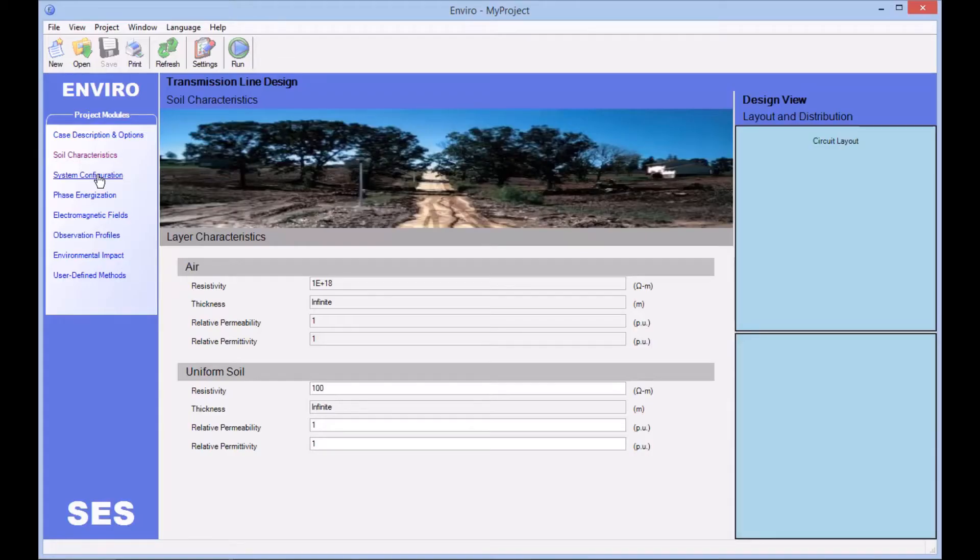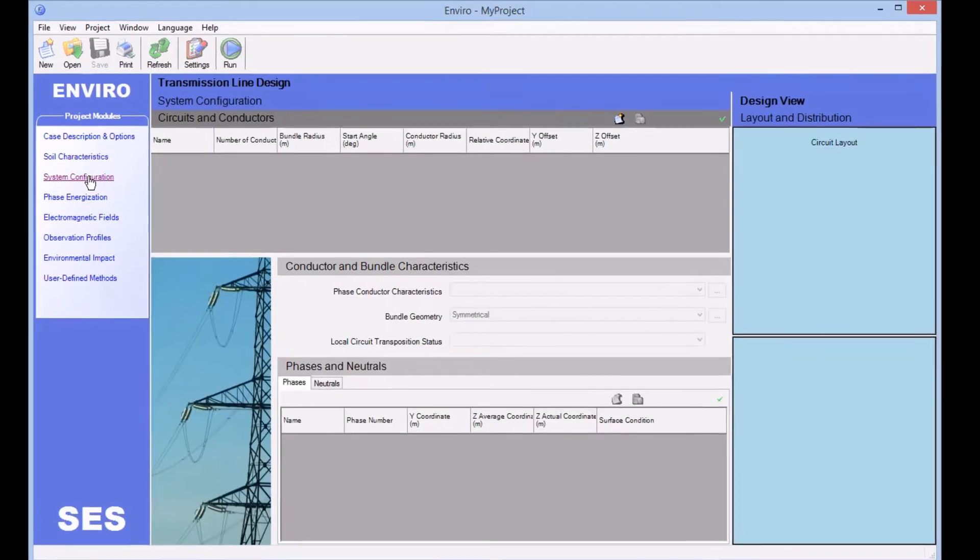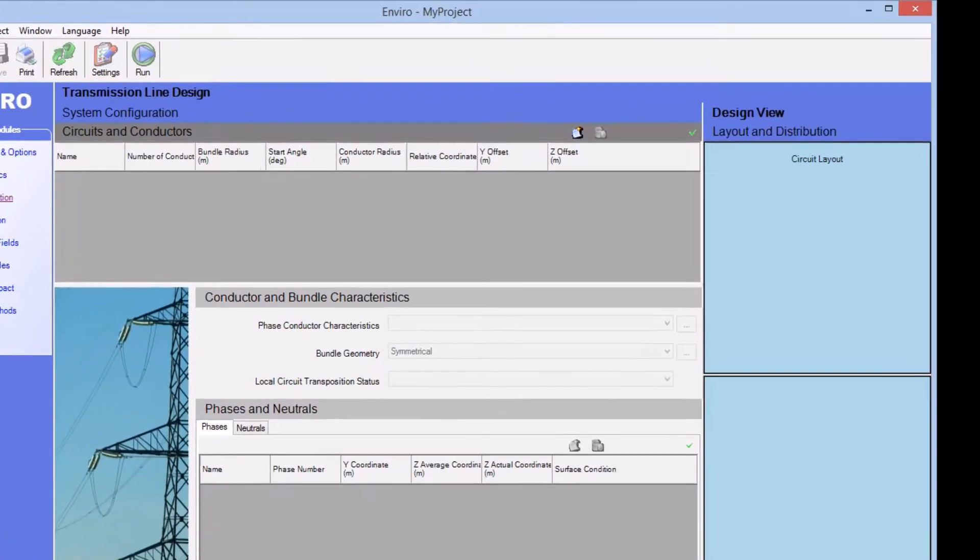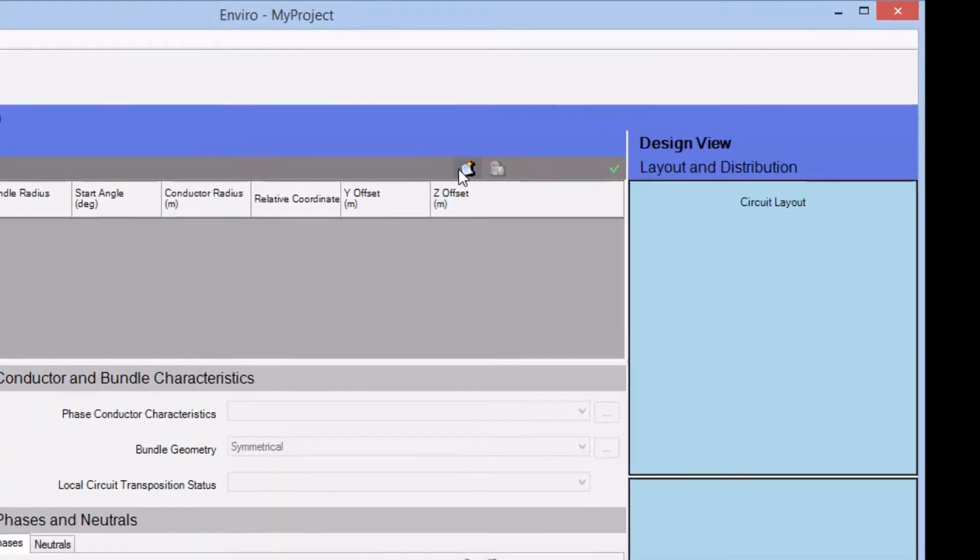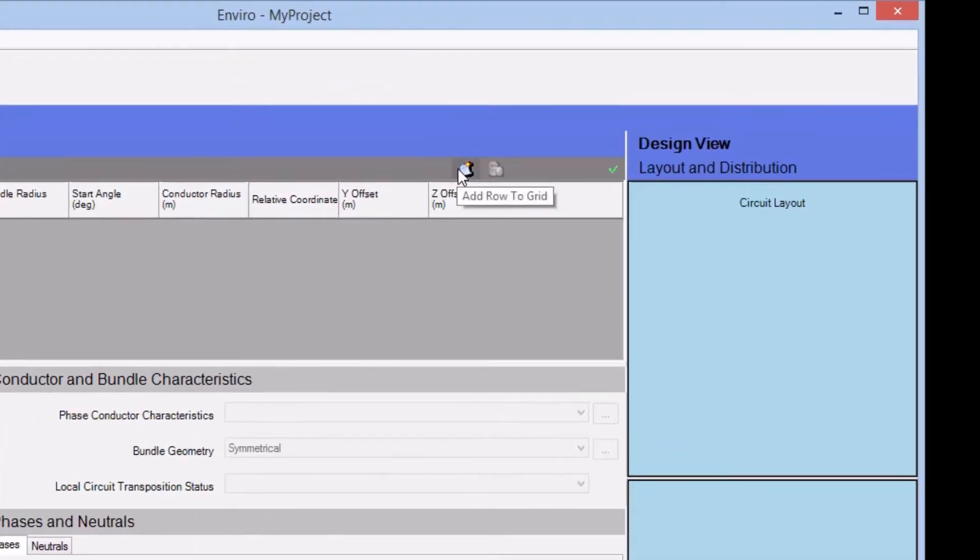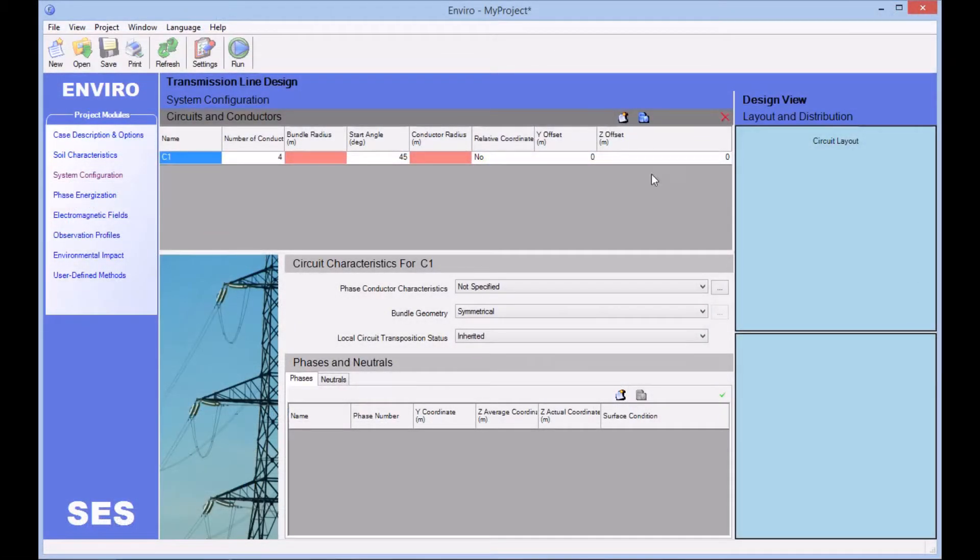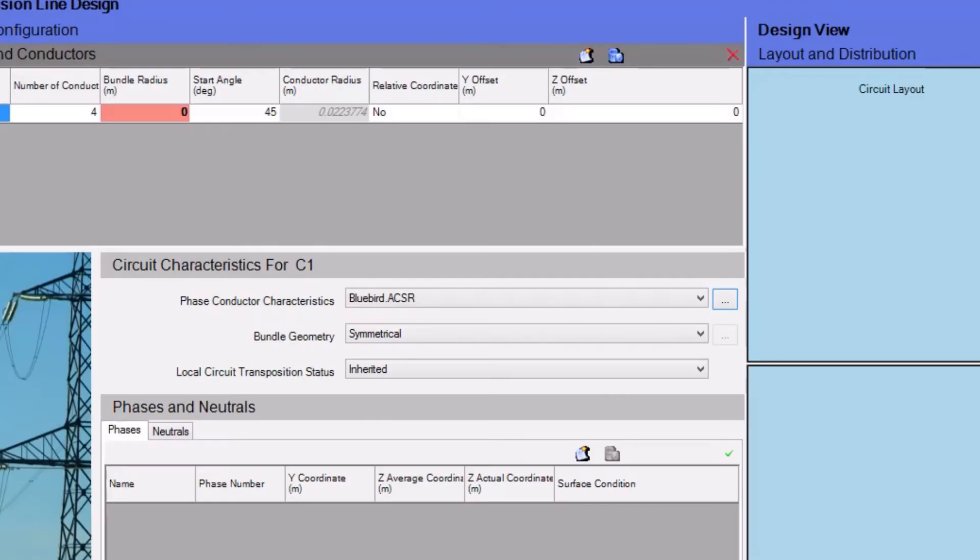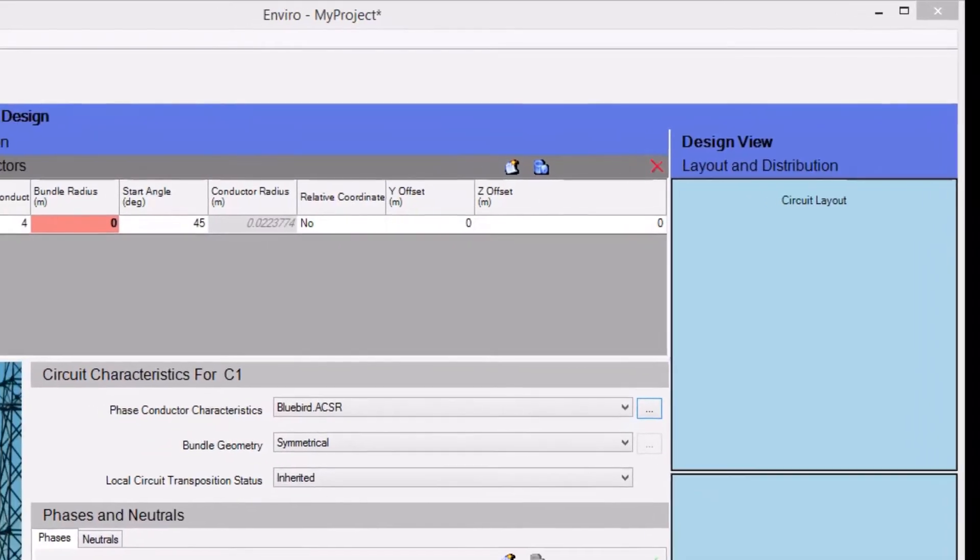Transmission line parameters are defined in the System Configuration module. To create a new circuit, you begin by clicking on the Add Row to Grid icon. And here we will import phase conductor characteristics from SES Library by clicking here. A separate video tutorial is available for showing how to filter and select items from SES Library, so we won't show those steps in this video. But we'll simply note that we've selected a bluebird conductor of the ACSR class from SES Library.